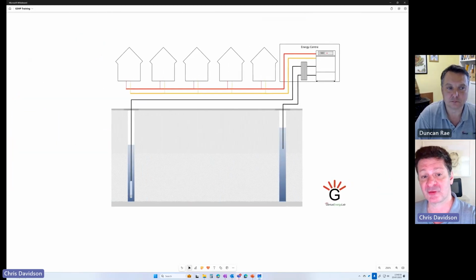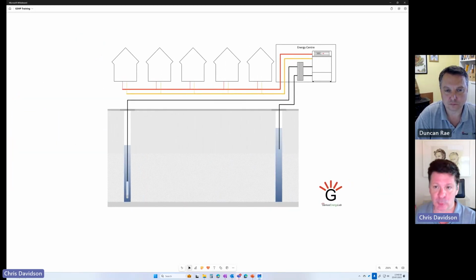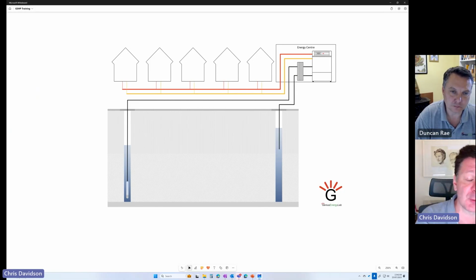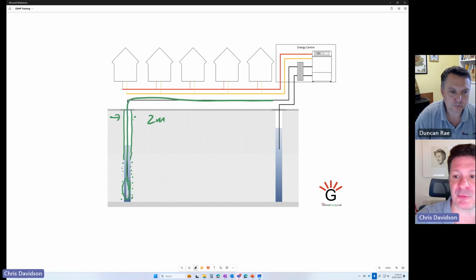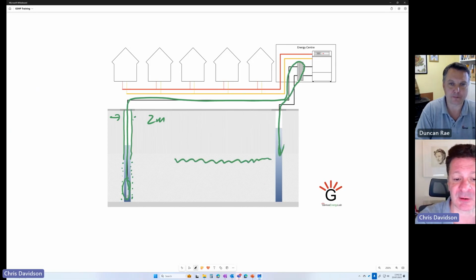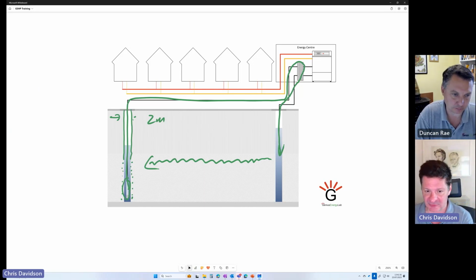We do have the alternative of open loop. So this is when we're taking water from the environment, warming it up or cooling it down and putting it back into the environment. Now these open loop boreholes are much bigger. They're water wells. They can be up to a couple of meters in diameter, for example, 2 meters in diameter. And they've got quite significant construction. So they'll be maybe steel lined down into the ground. They might have packing material here to filter that water. We've got pumps down the bottom, and those pumps pump up through a heat exchanger, warm it up or cool it down, as I say, and back into the ground again. And then in time, it will migrate across here. So it is a loop, but there's that open element to it.